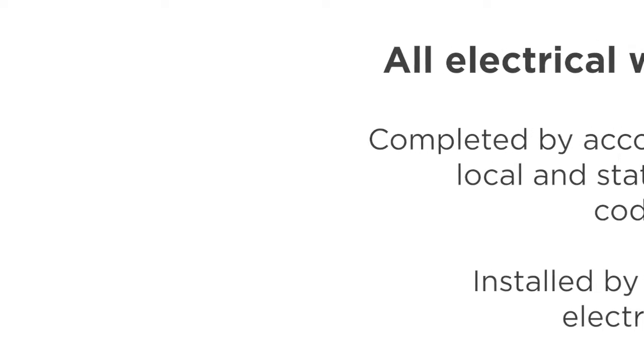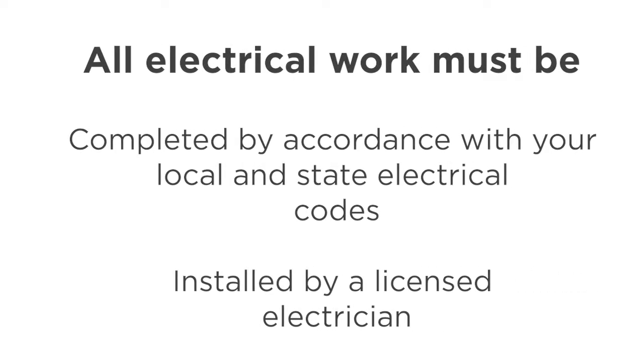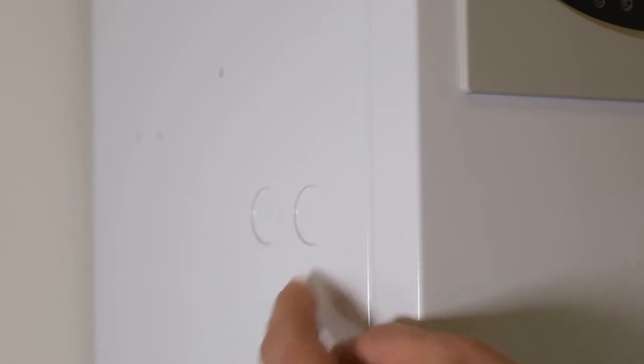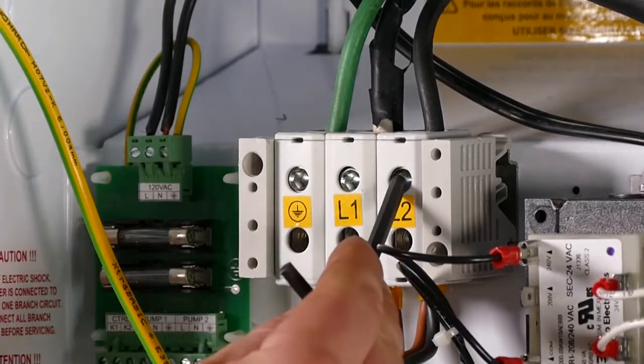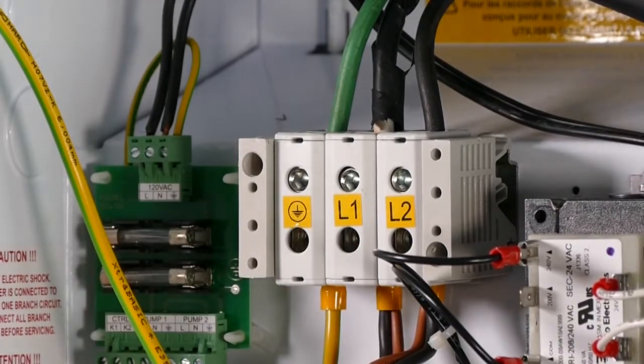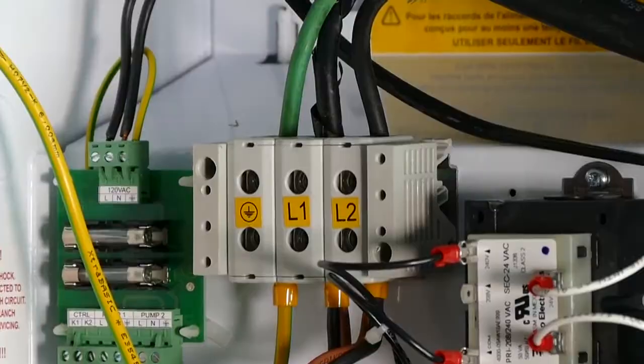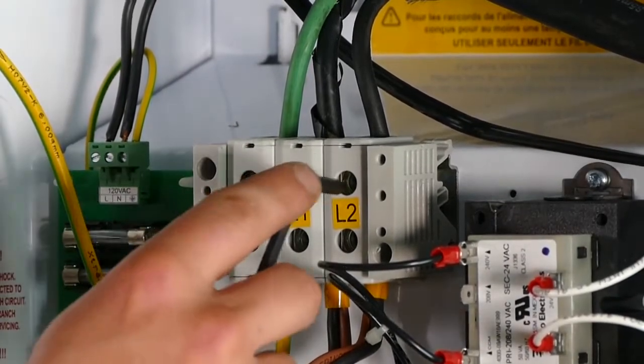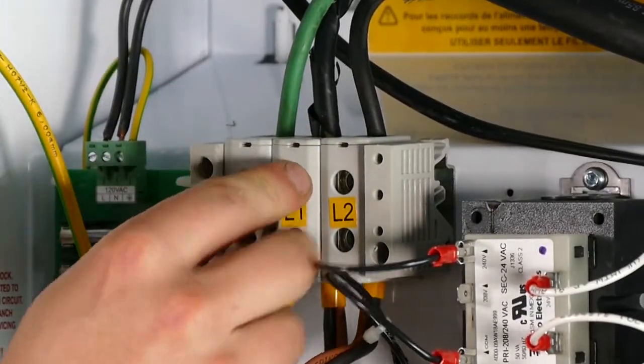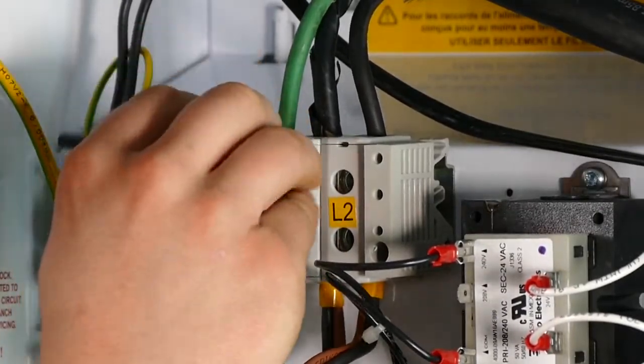All electrical work must be completed in accordance with your local and state electrical codes by a licensed electrician. Prepare the 240 volt cord and bring it into the boiler using one of the available 1/2 inch knockouts. Start by connecting the ground wire and tightening the wire into place using a 3/16 hex key tool. Then proceed to connect the L1 and the L2 wires. It is very important to take the time to carefully tighten the wires as thoroughly as possible.